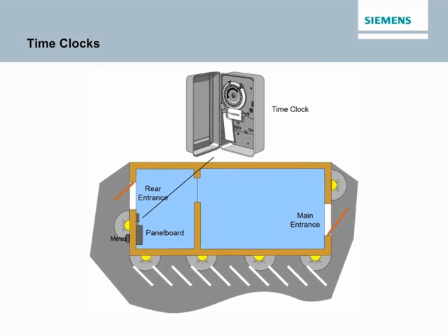Tork, Sangamo, or Paragon time clocks are available as an accessory for P-Series panel boards. Time clocks are available with 1-pole or 2-pole, single or double throw contacts, or 3-pole single throw contacts. They are rated for a maximum of 277 volts. A time clock can be used to turn on control of a branch circuit or an entire panel board. The accompanying illustration, for example, shows a time clock connected to a panel board that controls the outside lights for a small commercial building. This allows the lights to be turned on and off automatically at specific times.